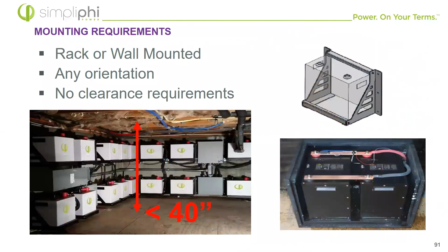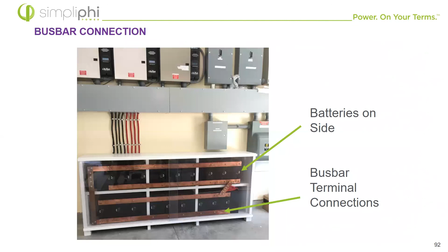It's also possible to use bus bars, as you can see in this photograph, with the batteries lying on their side. If you do this type of installation, make sure you size those bus bars correctly, since their ampacity is based on their dimensions or cross sections. Check your guide or speak with someone to make sure you're sizing them correctly, and there's no impedance or resistance issue. If sized correctly, you won't have that problem.